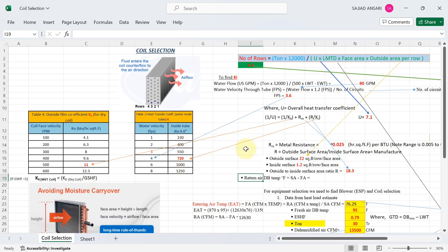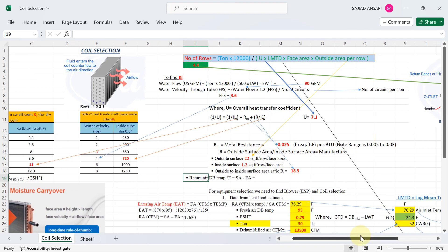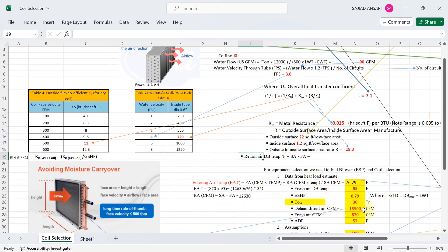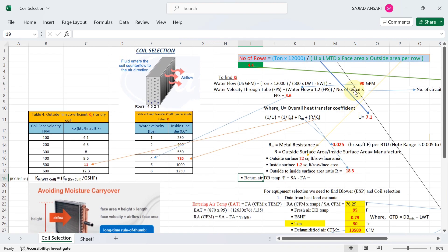Once you get the water velocity, you use it to look up the heat transfer coefficient ki from the table. To find water velocity through the tube, the formula is: Water flow × 1.2 fps ÷ number of circuits. Number of circuits per ton is always assumed as 1, so for 30 tons we have 30 circuits.